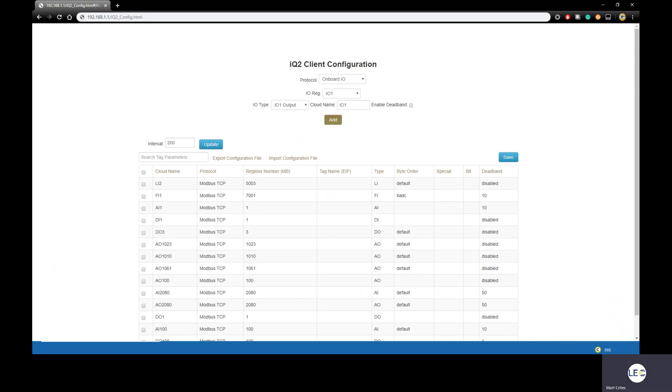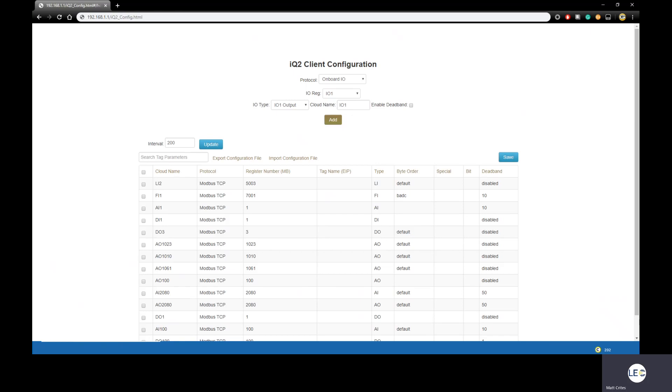The next option we'll want to configure is the interval. This value is how often you want the CloudGate to send all of your data values to IQ2. By default, we normally set it to around five minutes, but you can set that to any time frame you like. Just keep in mind, the more often you send values to IQ2, the more cellular data will be consumed. Currently, I have mine set for 300 seconds, so I'll just leave that alone.